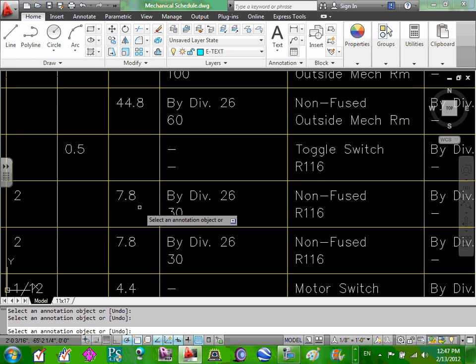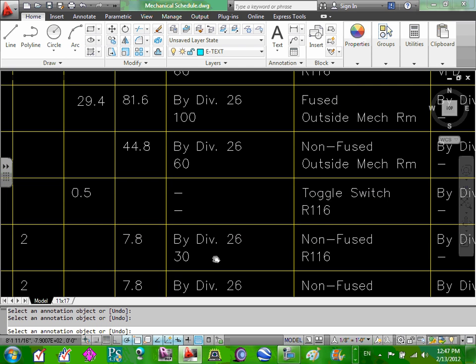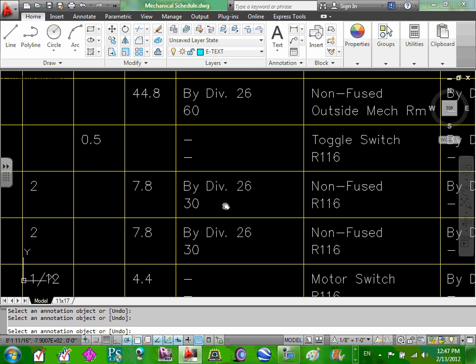430.250. Okay, now let's look at what they're asking us here. This is a disconnect. Do they need a disconnect? Let's look at the boiler located in the mechanical room, division 16 to provide combination starter/disconnect adjacent to the unit. Do they need a disconnect? Yes. Did they say fused disconnect? No. A combination starter disconnect. So I need a disconnect.